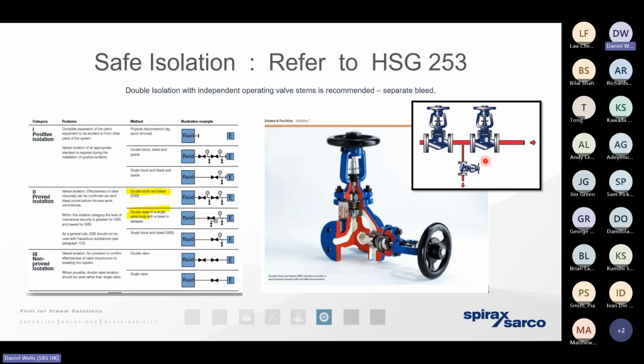The question is, how do we know that that primary valve has failed, and how do we know that the secondary valve isn't going to do the same? Well, we pull those 2 valves apart and we've got a third valve in the middle. It's what we call a bleed valve or a telltale. So when these 2 valves are locked off, this valve's in the fully open position. Any steam that's passing across this first valve is going to follow that pressure drop principle we spoke about. It's going to be diverted away.